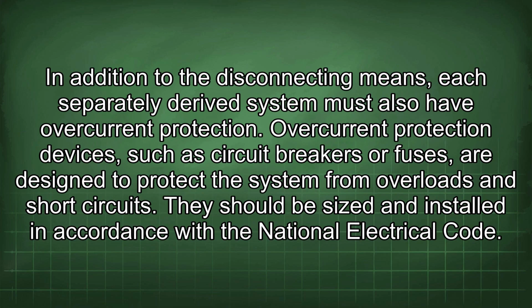In addition to the disconnecting means, each separately derived system must also have overcurrent protection. Overcurrent protection devices, such as circuit breakers or fuses, are designed to protect the system from overloads and short circuits. They should be sized and installed in accordance with the National Electrical Code.